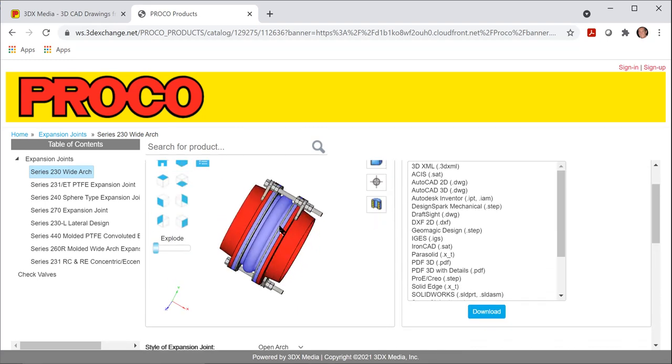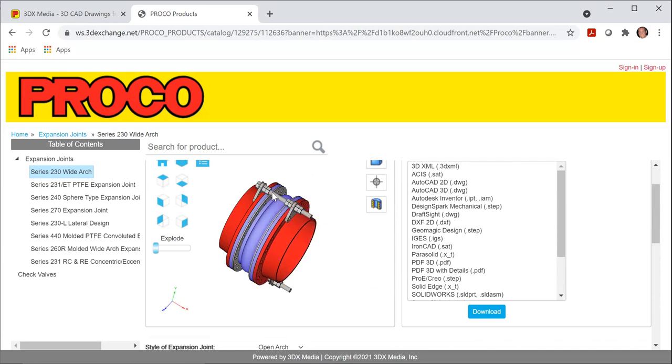Here's the drawing a little bit, and you'll notice that there's nuts on the inside. So these nuts are going to prevent over compression if there is a check valve, strainer, the weight of the column of the pipe pushing down the joint, it's going to prevent that over compression.